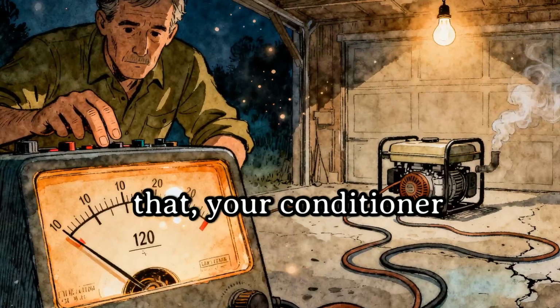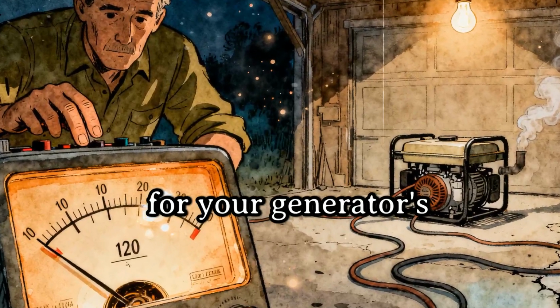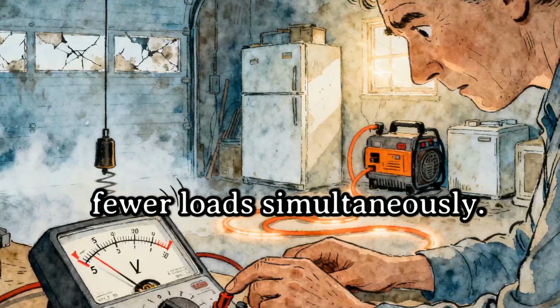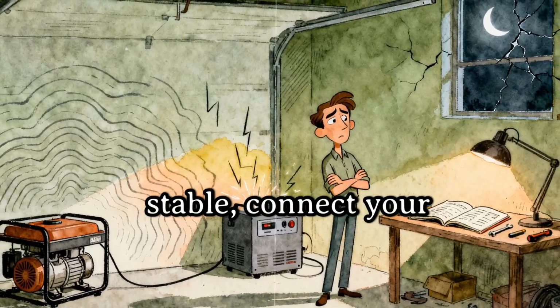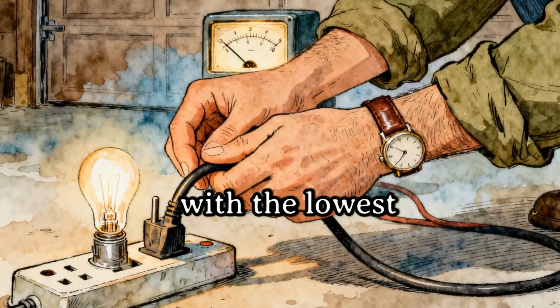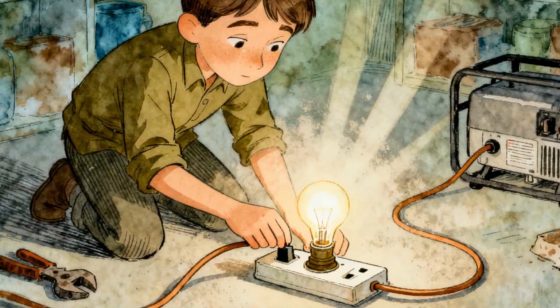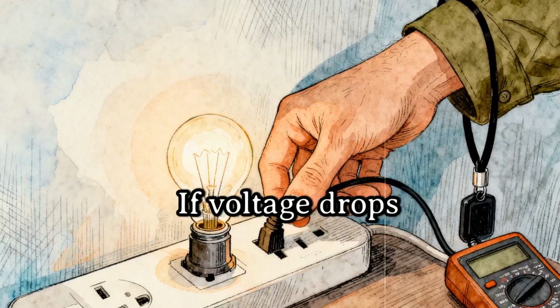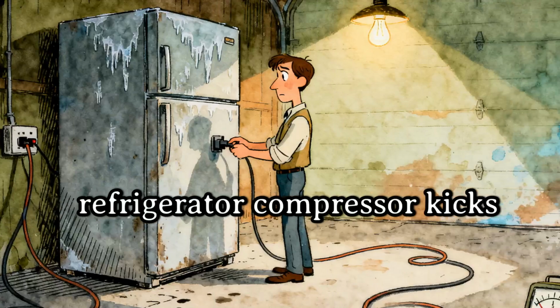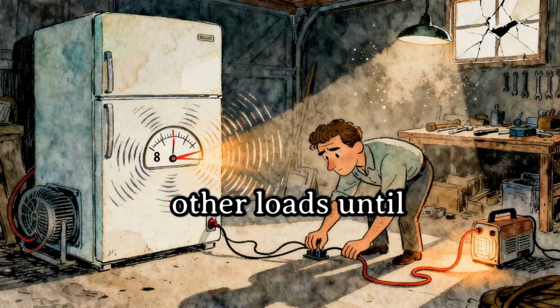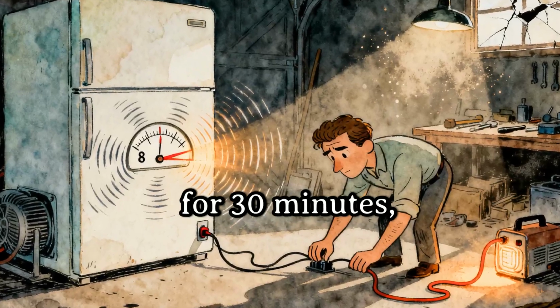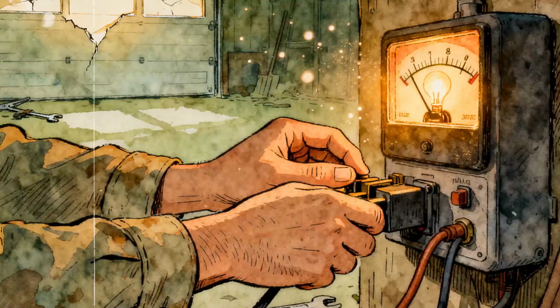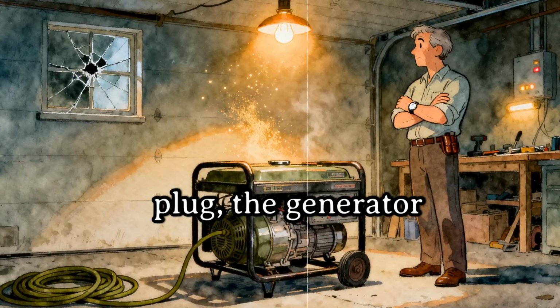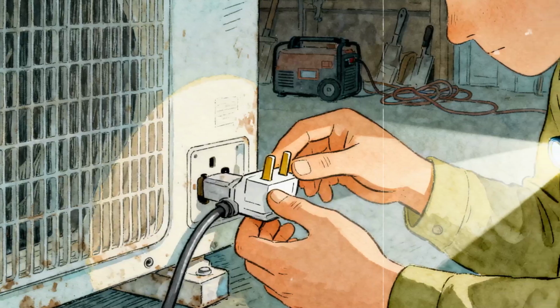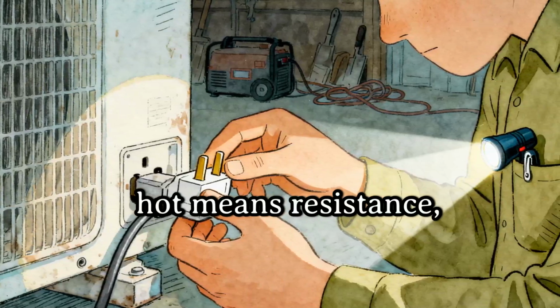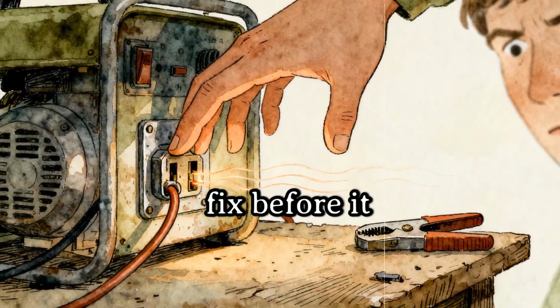If the reading swings more than that, your conditioner may be undersized for your generator's output instability, and you should run fewer loads simultaneously. Once voltage is stable, connect your appliances one at a time, starting with the lowest wattage device and finishing with the highest. Watch the meter for each addition. If voltage drops more than 8 volts when the refrigerator compressor kicks on, reduce your other loads until it stabilizes. Run the system for 30 minutes, then physically check every connection point, the conditioner's input plug, the generator outlet, the grounding clamp, for heat. Warm is acceptable. Hot means resistance, and resistance means a loose connection you need to fix before it arcs.